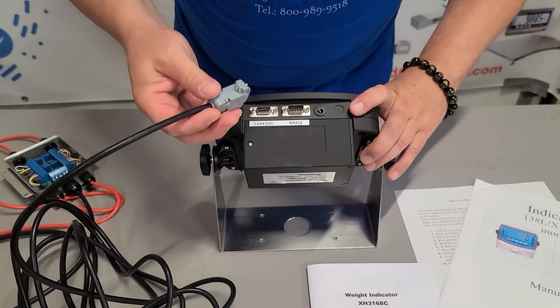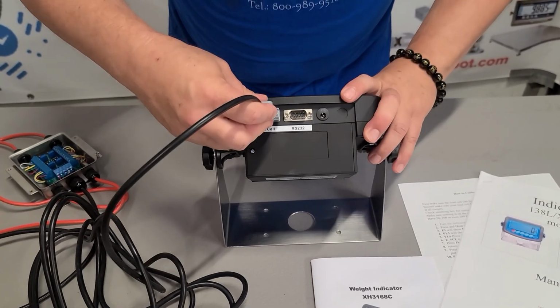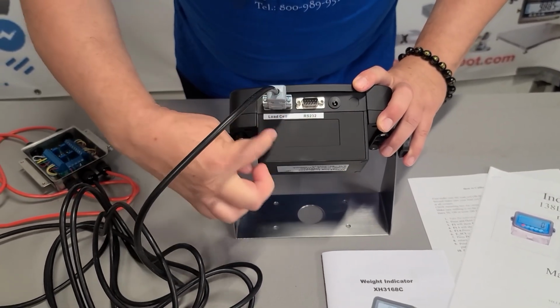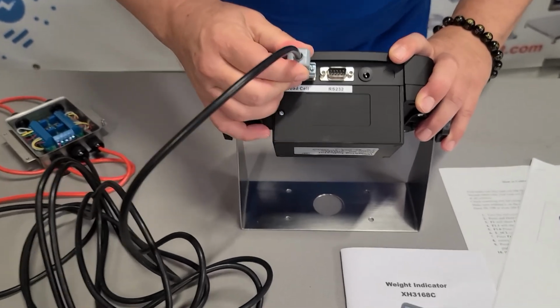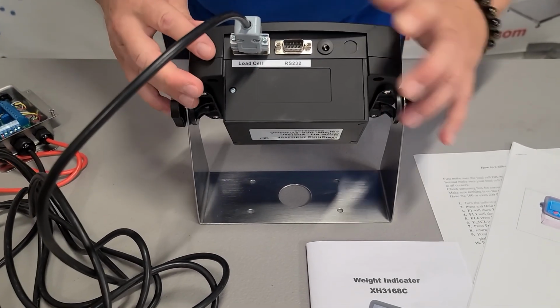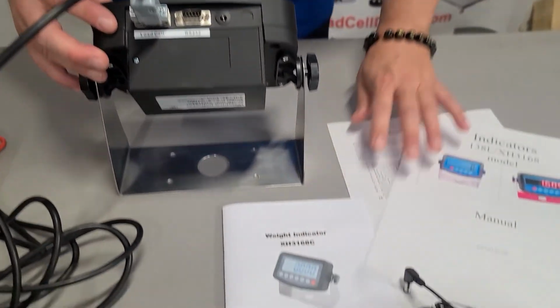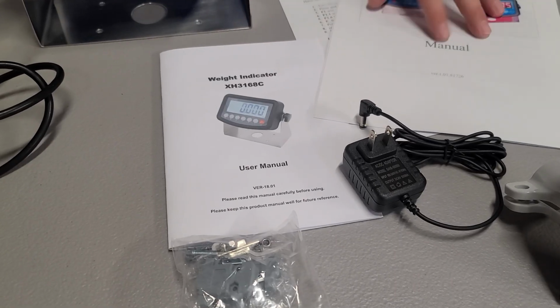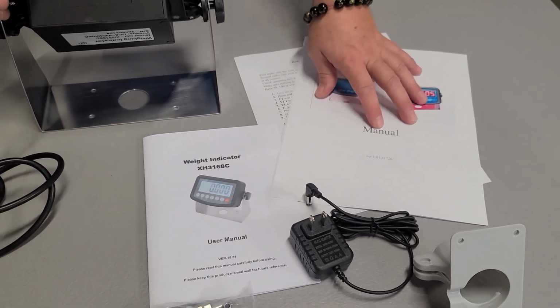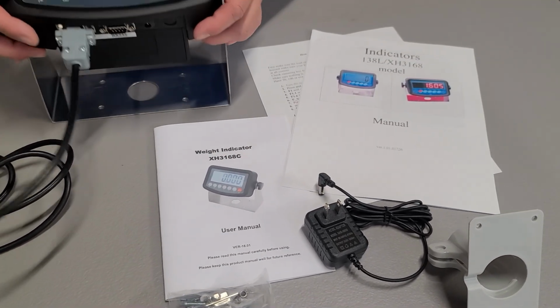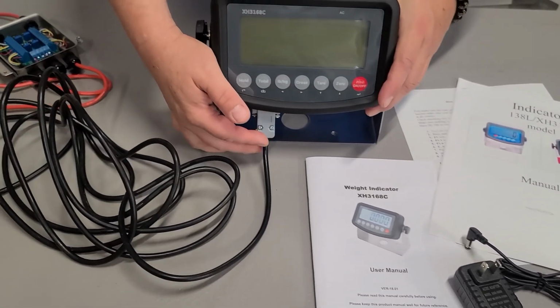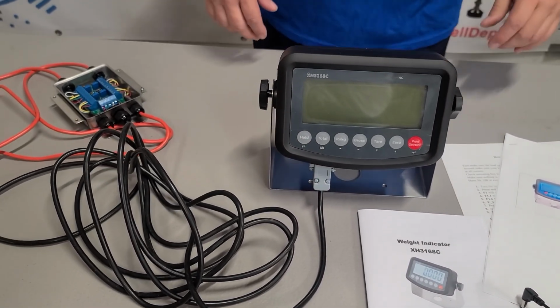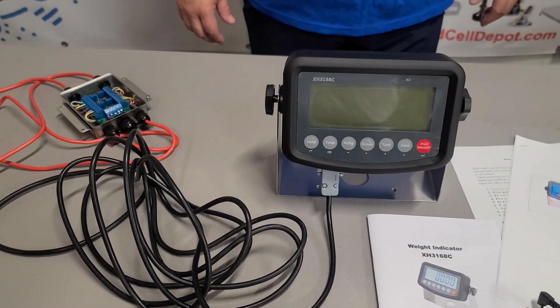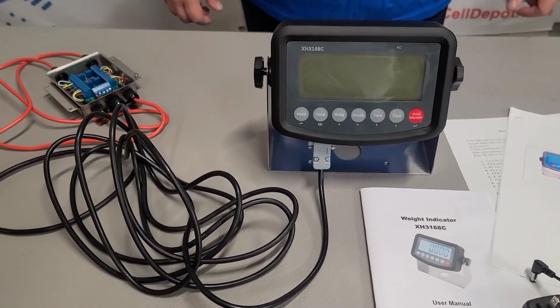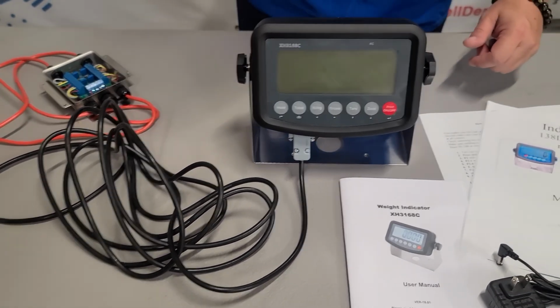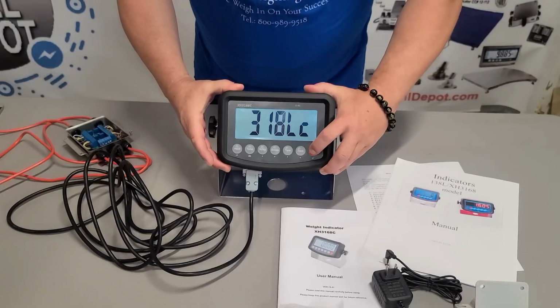Load cell connector goes right in here. The large battery compartment is here on the bottom, and there's an AC adapter port, which also comes with the indicator. The indicator comes with two different manuals, one that I make when you put a scale kit together, and the one that comes from the manufacturer. Now, in this case, we're going to use a test weight to do a calibration. So first, we're going to turn on the indicator.